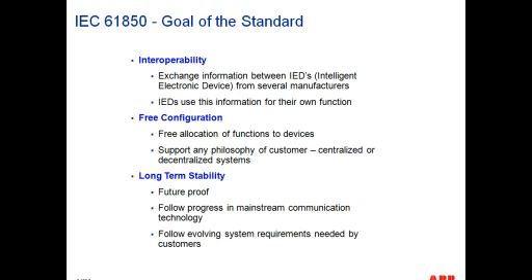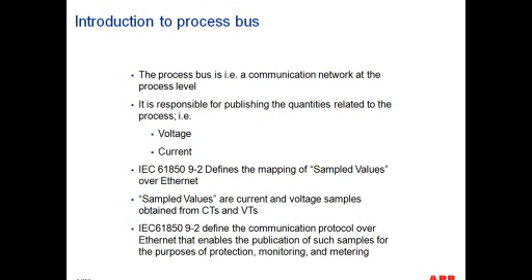So today, the standard media that IEC 61850 prescribes is 100BASE-FX, which is Ethernet fiber optic with a bandwidth of 100 megabits per second. The idea is that if a few years from now that changes to something else, the standard is flexible enough that we'll be able to prescribe or recommend that type of media as well, so that the standard continues to evolve with the rapid changes of technology. And the structure of the standard was put together in different sections in such a way that this evolution is facilitated. So now let's talk about the process bus.